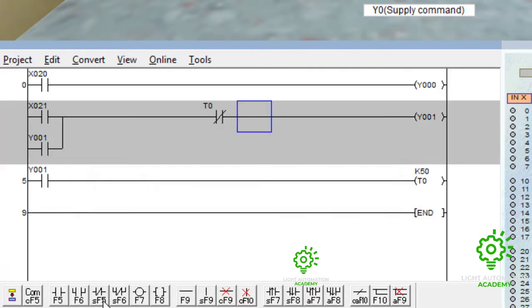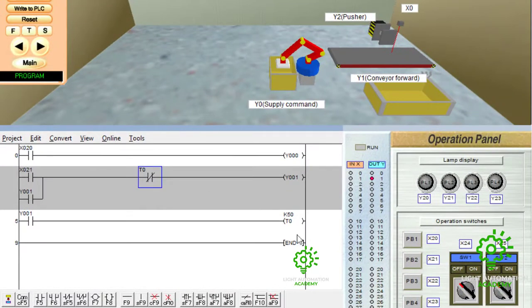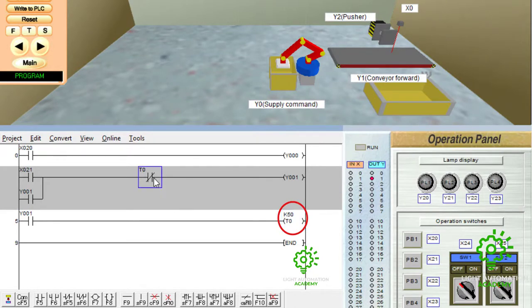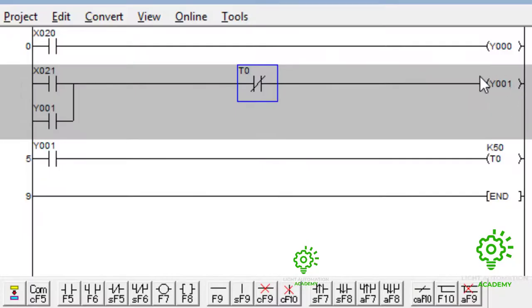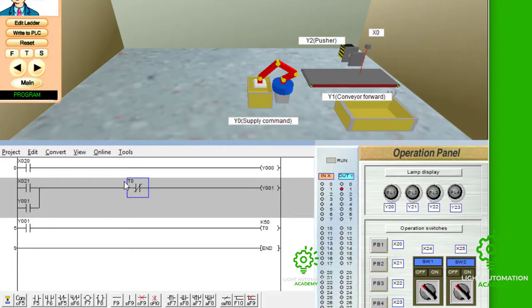Now, at default, it is normally close. This address T0, which belongs to this. So, what we are trying to achieve is this. After T0 has counted 50, its state will change here from normally close to normally open, which will break the signal that is coming from this side. And by then, our Y1, which is the conveyor, is going to stop working.